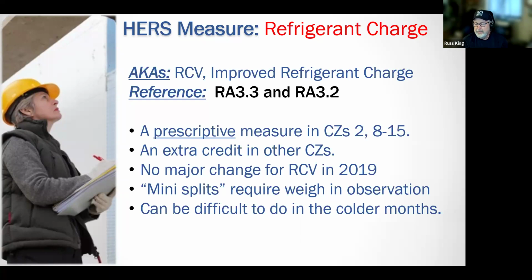All right. Even though I'm a huge fan of this verification, I think the HVAC industry brought this on themselves by doing a horrible job charging systems. And ever since HERS raters have started verifying these systems, they've done a much better job. The problem is that certain types of equipment are very difficult. Mini splits in particular can be very difficult. And you can only do this test when it's a certain temperature outside. And so coordination can get very, very tricky on this. All right. But I do think if you can pass this test, you should do this test.